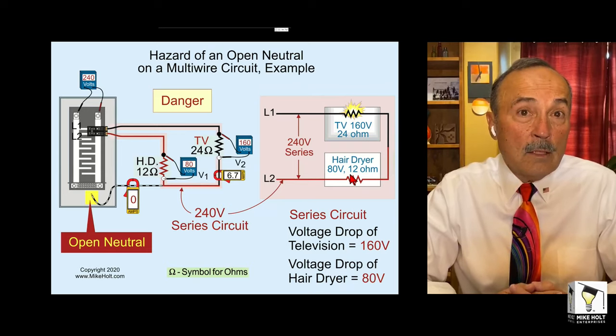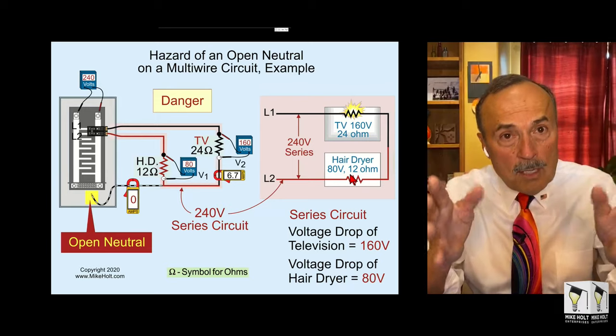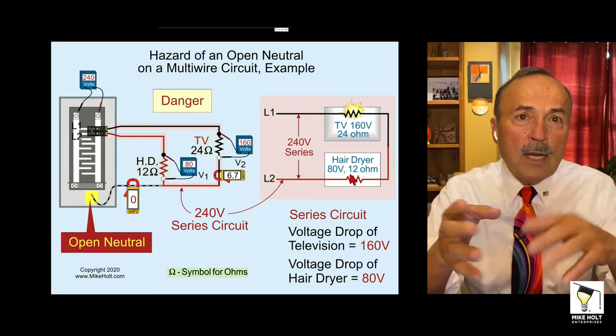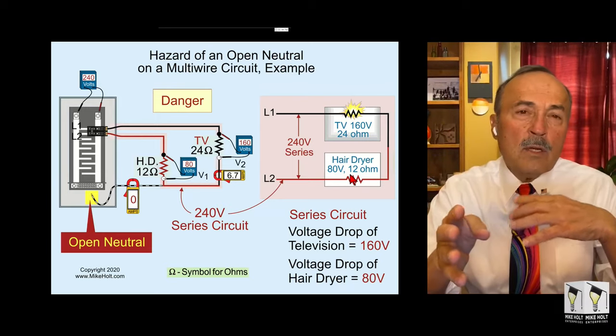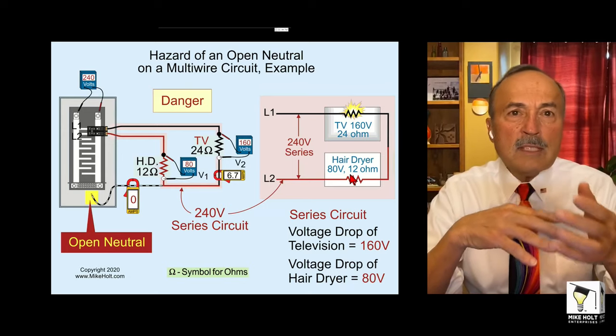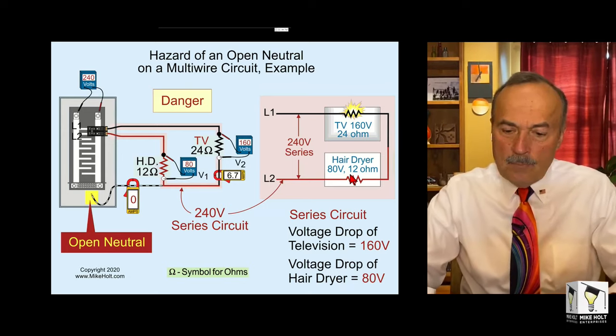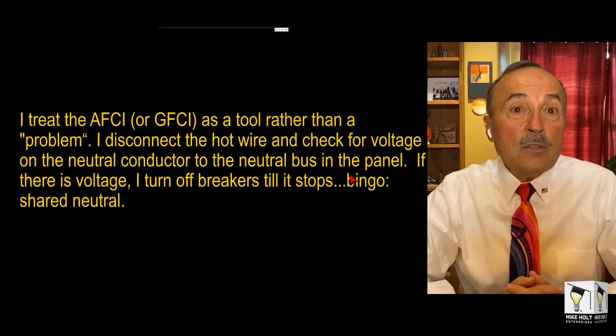That's the way it's going to work out. Just talking about multi-wire branch circuits, the advantage of multi-wire branch circuits is you have one less wire. We talked previously, it's going to be 50% less voltage drop. Let's go on. Here's what the guy said.